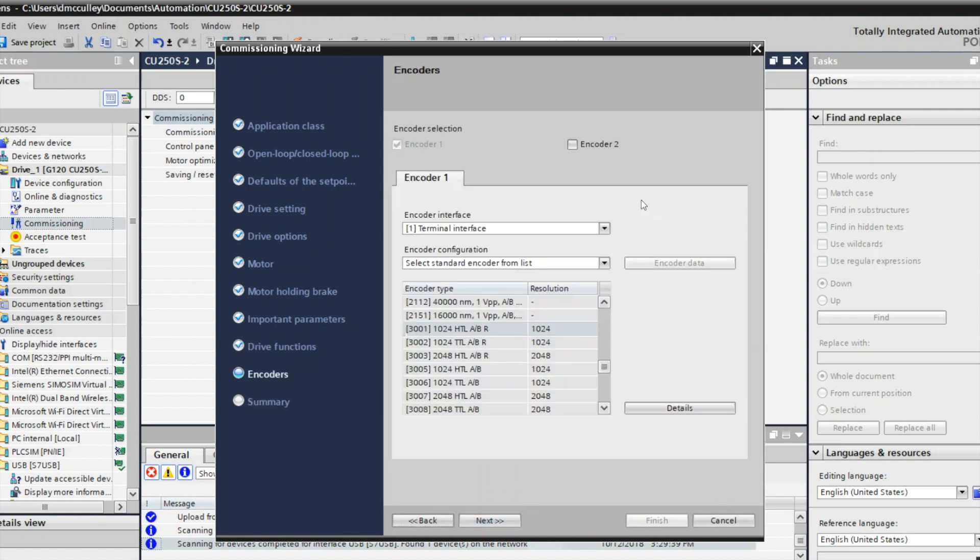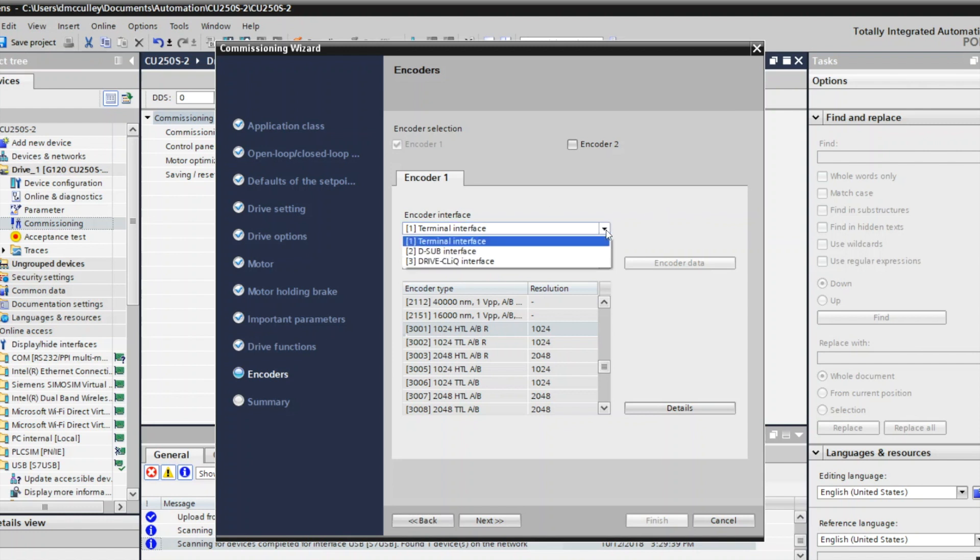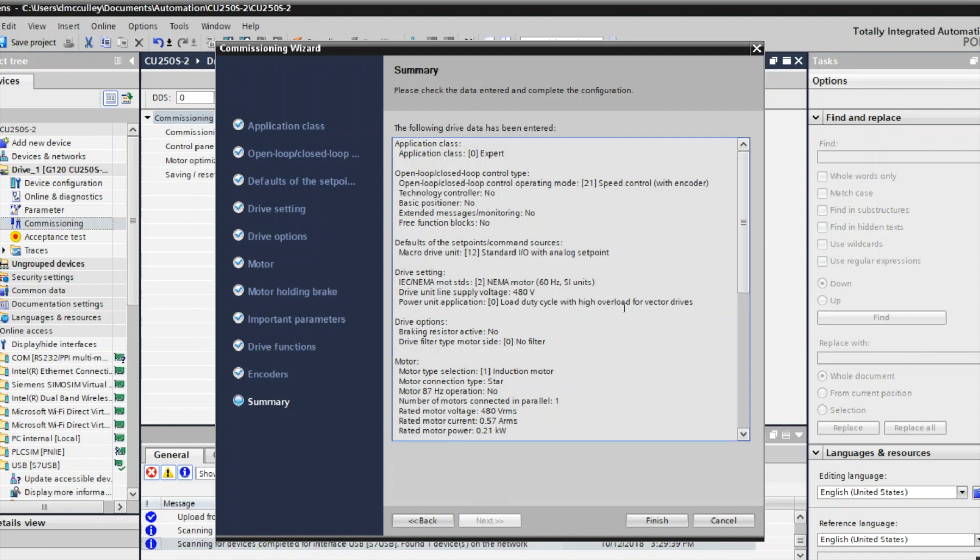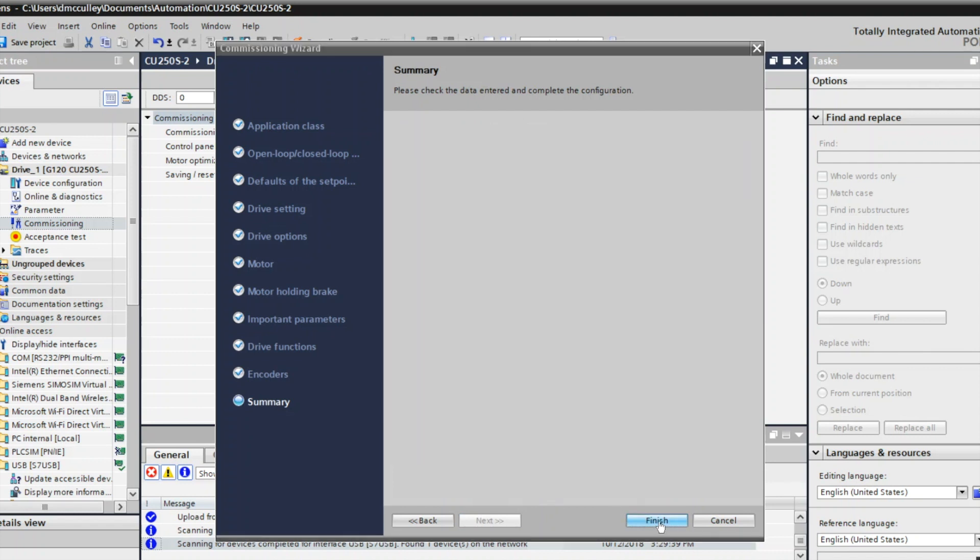Now here's the encoder information. There are three ways that you can connect your encoder to this CU250S-2 control unit: one is the terminal interface, the other is using the D-sub connector on the bottom of the control unit, and another is if you have a Drive-Cliq encoder you can connect it with the Drive-Cliq interface. I'll assume mine's a terminal interface and a 1024 HTL encoder. That completes my commissioning wizard.